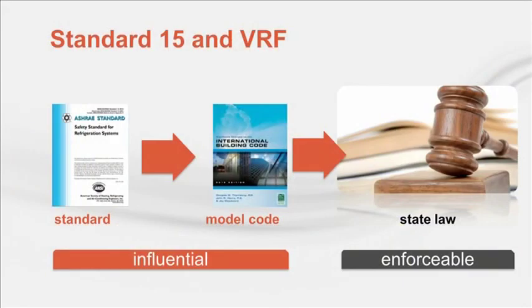Typically, this is a 2-step process. Model code agencies, such as the International Code Council, look to industry standards and other materials for best practices. They combine these into model codes. The final step is for a state or other governing body to adopt the model code into law. These laws, or codes, are then enforced by the building inspectors. It's important to understand this process because several years can pass between the publication of a standard and its incorporation into a state code. Changes in wording and sometimes intent occur along the way. So, bottom line, when applying Standard 15, be sure to also check the local codes.